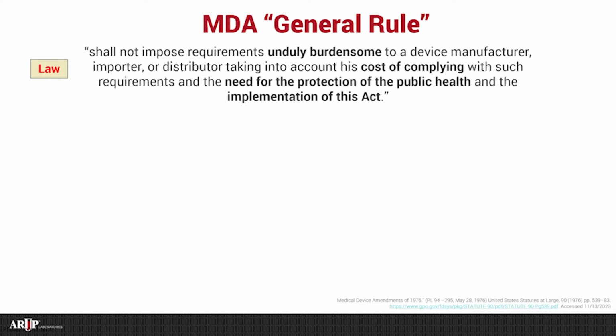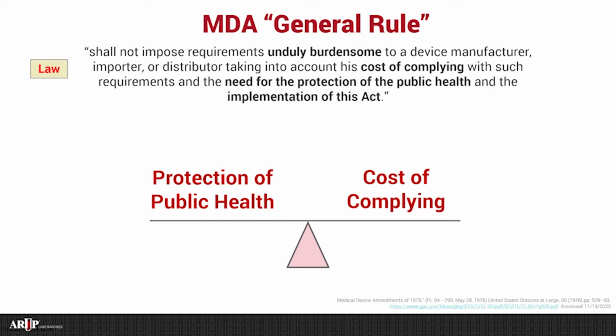There's another item as part of that law, the Medical Device Amendments, that's really important. It's called the general rule in the law, and I'll read it because I think it's so important. The FDA shall not impose requirements that are unduly burdensome to a device manufacturer, importer, or distributor, taking into account his cost of complying with such requirements and the need for the protection of public health and the implementation of this act. Let's unpack this statement a little bit and think about what this really means. And again, this is law. This isn't just my opinion.